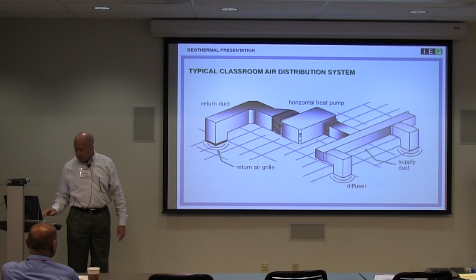We've done thousands of classrooms with heat pumps sitting above a lay-in ceiling just like this one, with no insulation—the only thing between us and the heat pump is a ceiling tile. It's been very successful; we very seldom get a complaint. And if we do, it's typically because the system hasn't been balanced yet and we're moving too much air, which would happen with any system.